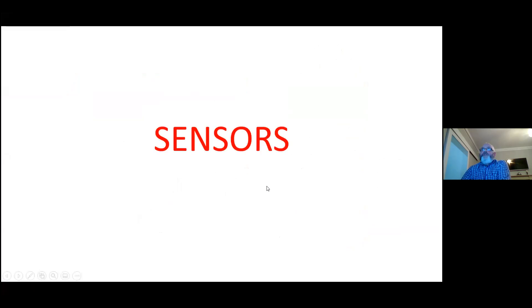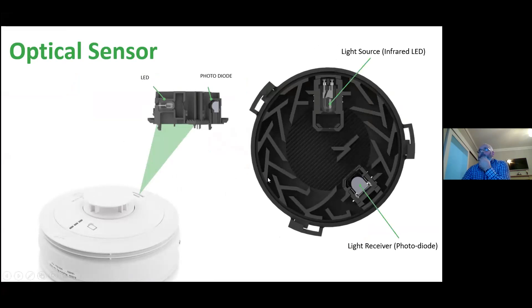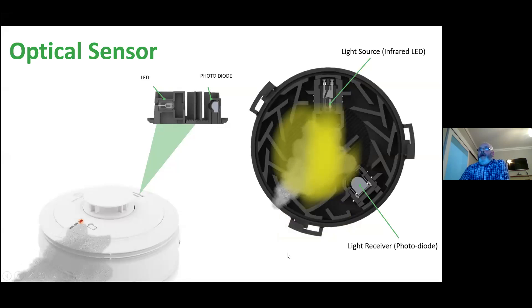If we look at the sensors in relation to fire detection and the way we have progressed from the standard sensors themselves — the optical sensor. Basically what you have in an optical sensor is a light source that beams a beam of light to the opposite end of the chamber every 10 seconds. You have a light receiver protected by baffles so that the beam originally coming down won't get into that section. But if you have smoke being transmitted into the chamber itself, you get what they call the light scattering principle, and eventually light will get into the receiver when your obscuration level becomes at a certain height. Under the standards, the obscuration level has to be between 2 and 4%, and we trigger ours at 3% obscuration level. When that happens, the unit goes into alarm and sets off your system.